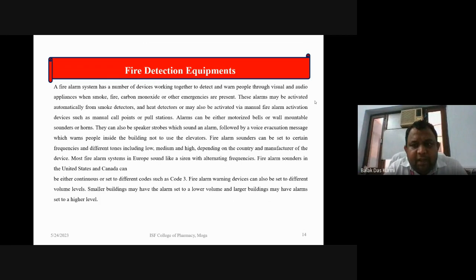Alarms can be either motorized bells or wall-mountable sounders or horns. They can also be speaker-based sounders and alarms, followed by a voice evacuation message which warns people inside the building not to use the elevators. Fire alarm sounders can be set to certain frequencies and different tones, including low, medium, and high, depending on the country and manufacturer of the device.